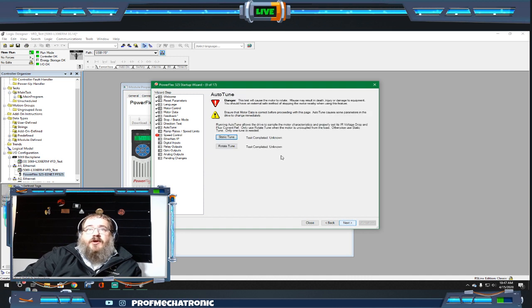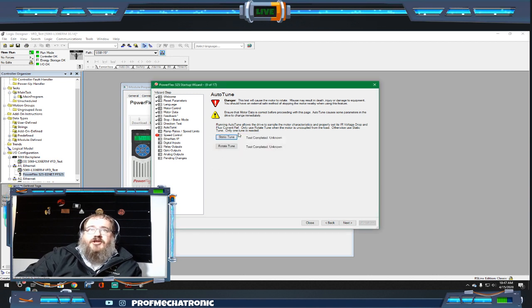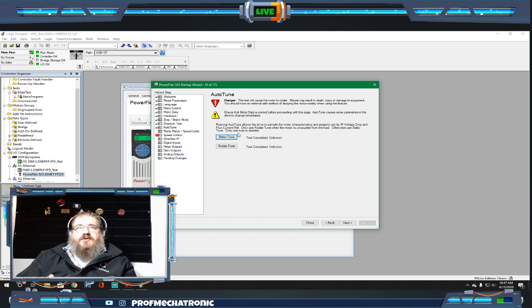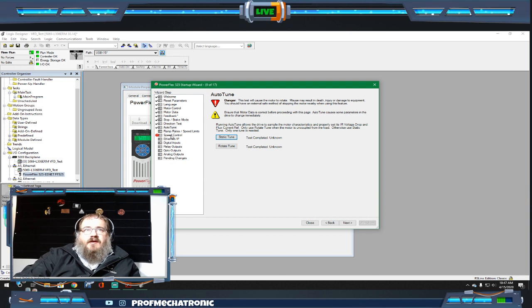We have the ability to do an auto tune. An auto tune takes all the information from the actual motor itself, where we can tune the drive parameters to match the type of motor. It's a very handy feature to do some static tuning and some rotate tunes. Basically, it saturates the motor, looks for feedback on the lines, does an IR voltage drop, does some flux calculations on the current. So it's able to take a lot of that information from the motor and optimize the setup from that.